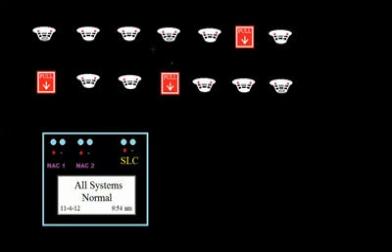So for all of our initiating devices, we can use just this one data loop. There are limits to how many devices can be on one of these, and that's panel specific, so it would depend on what kind of panel you're dealing with. It totally varies, but let's say for our purposes I could fit 100 detectors on here and 100 modules. A detector would be an addressable smoke detector, heat detector, or possibly a duct detector, and I think that's probably about it.